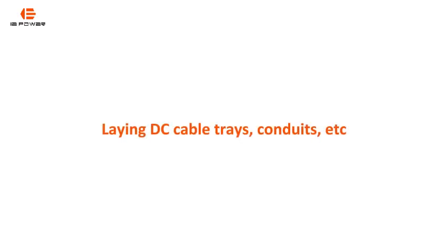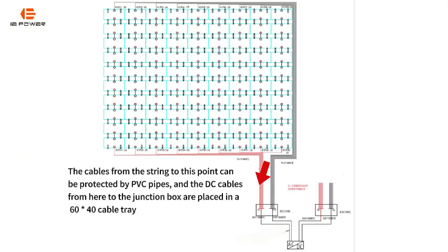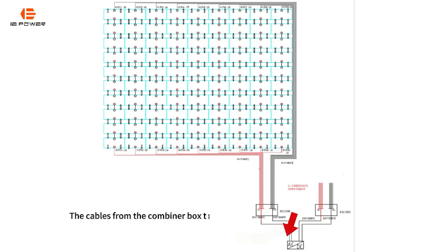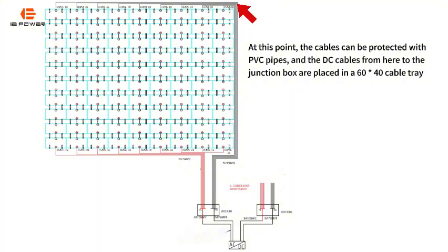Laying DC cable trays, conduits, etc. The cables from the string to this point can be protected by PVC pipes, and the DC cables from here to the junction box are placed in a 60x40 cable tray. The cables from the combiner box to the inverter are wrapped in corrugated pipes. At this point, the cables can be protected with PVC pipes, and the DC cables from here to the junction box are placed in a 60x40 cable tray.